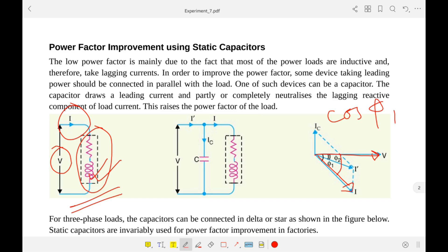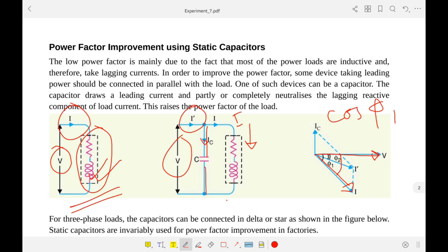So cos(phi 1) is our power factor without improvement, which is very low. To increase the power factor we need devices that take leading current — that is, supply reactive power. One such device is a capacitor. If we apply a capacitor in parallel with the load, it will take leading current.